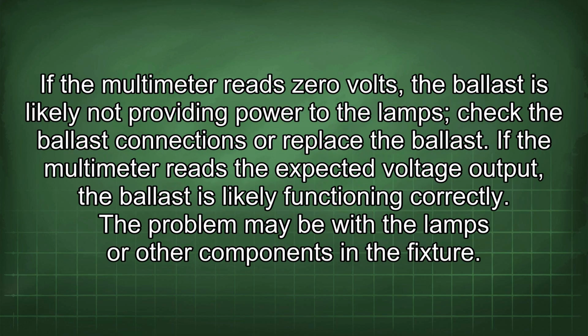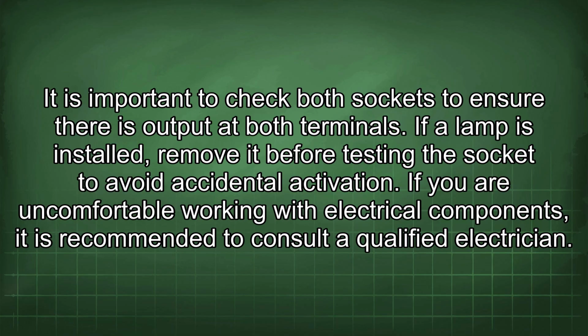If the multimeter reads 0 volts, the ballast is likely not providing power to the lamps. Check the ballast connections or replace the ballast. If the multimeter reads the expected voltage output, the ballast is likely functioning correctly. The problem may be with the lamps or other components in the fixture. It is important to check both sockets to ensure there is output at both terminals.